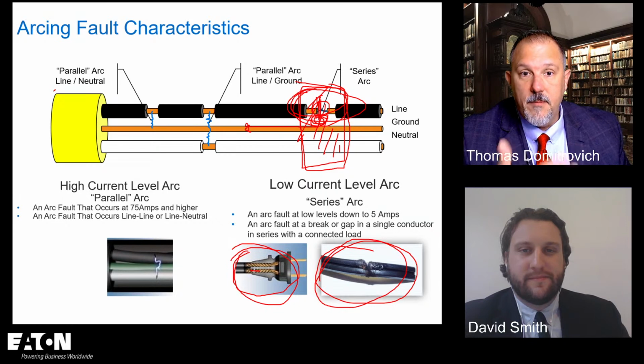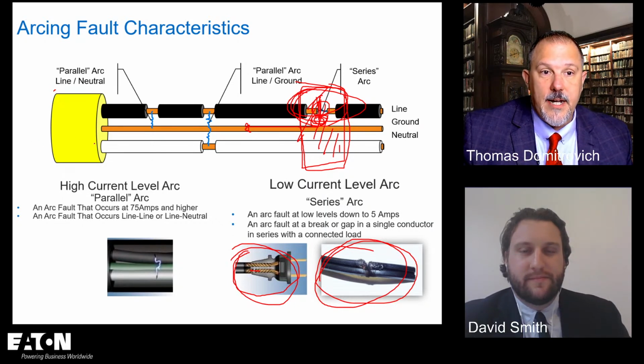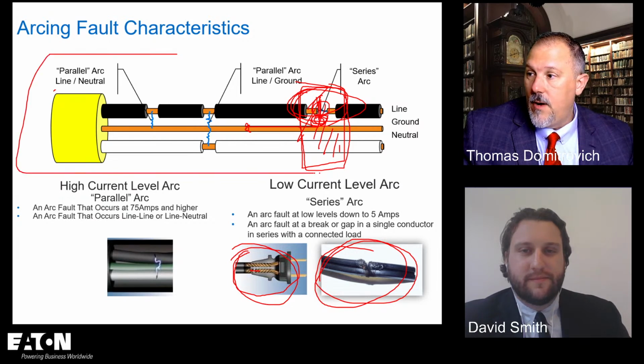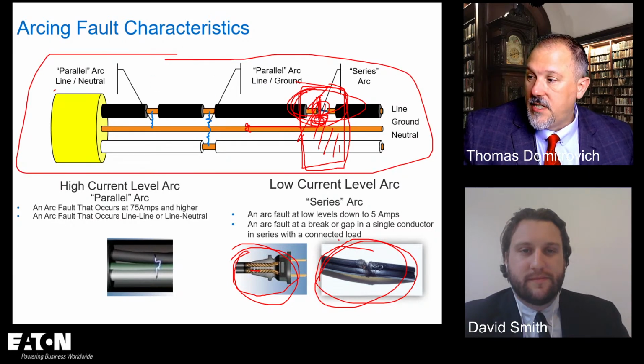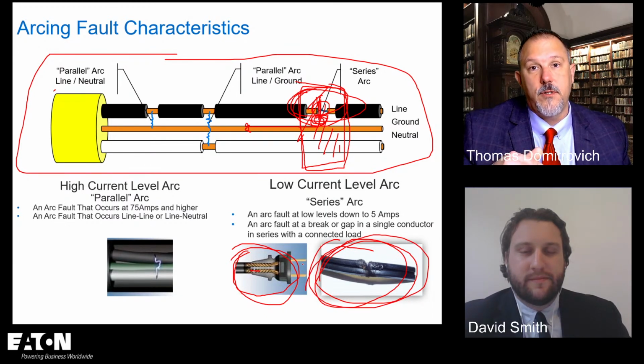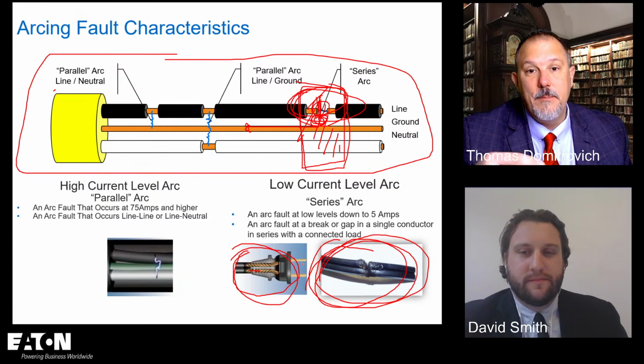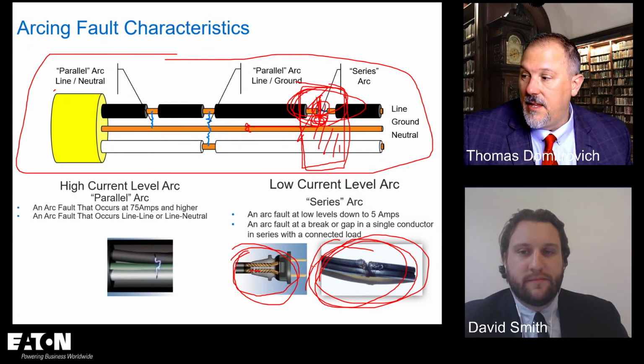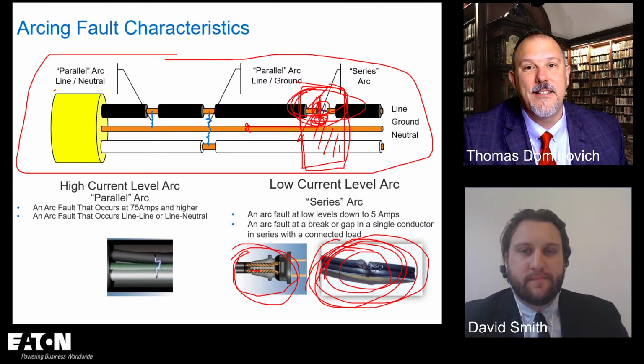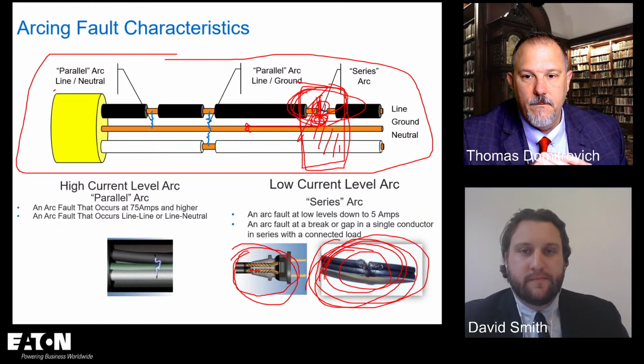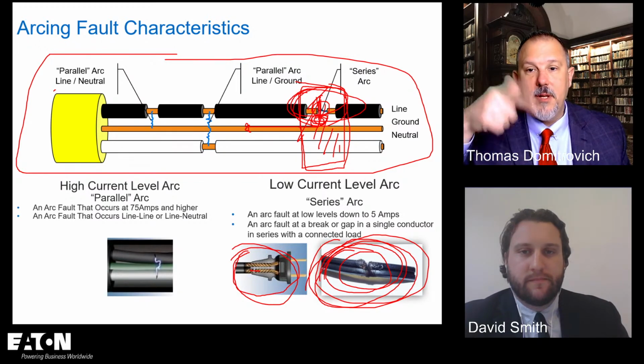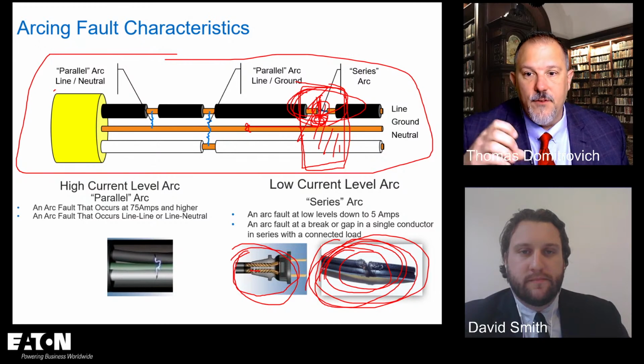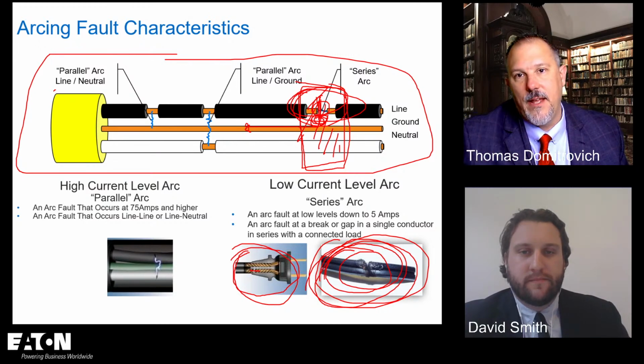So the AFCI combination, or the branch feeder, will protect all of these conductors. Your NM wire, that's what we were targeting, and it'll protect these connected cords for parallel arcing faults. What the combination type did was introduce the ability to detect a 5 amp series arc in SPT2 cord. That's the only test that is in addition to a branch feeder. You have to cut one of those conductors in an SPT2 cord, wrap it with tape, condition it with a high voltage to get some carbon buildup, and then you run a test at 5 amps, not at 75.